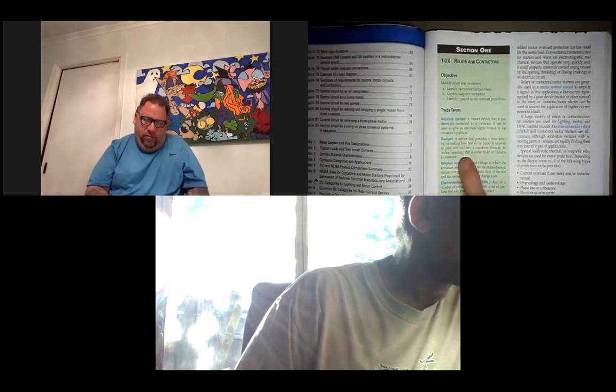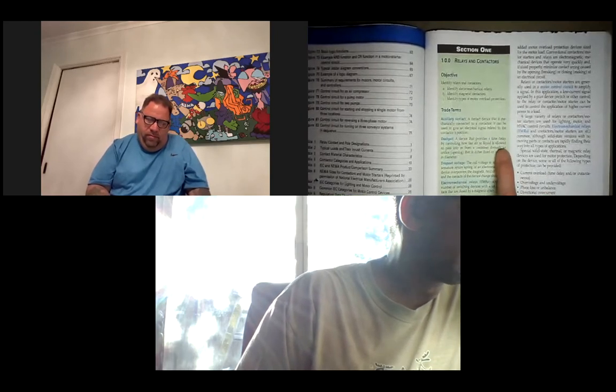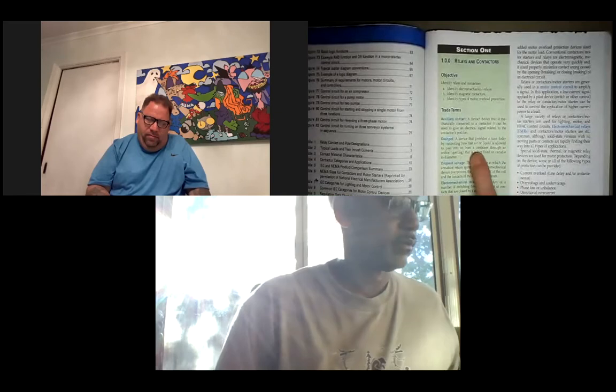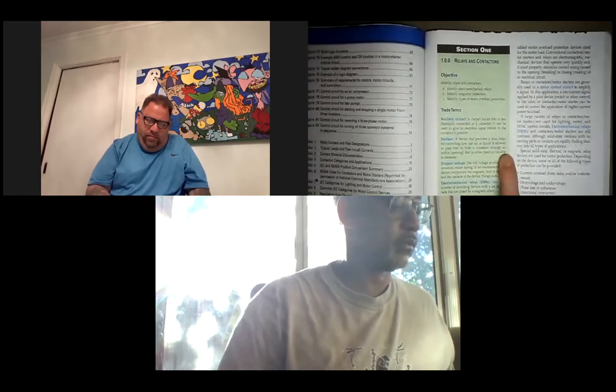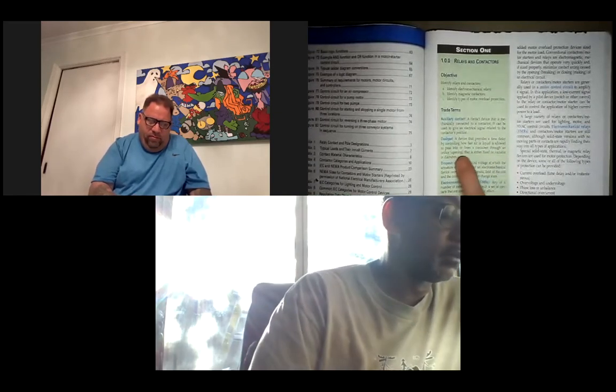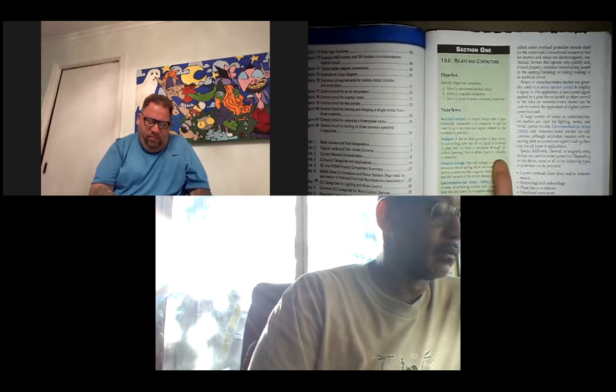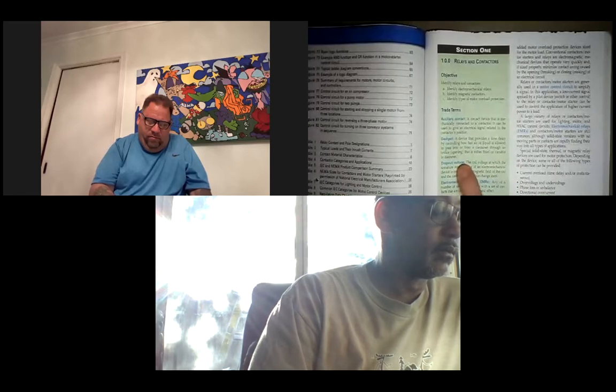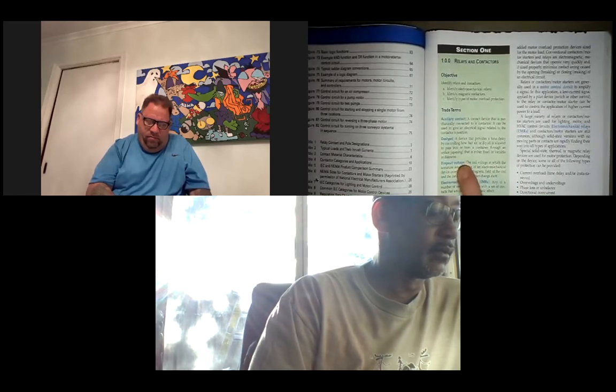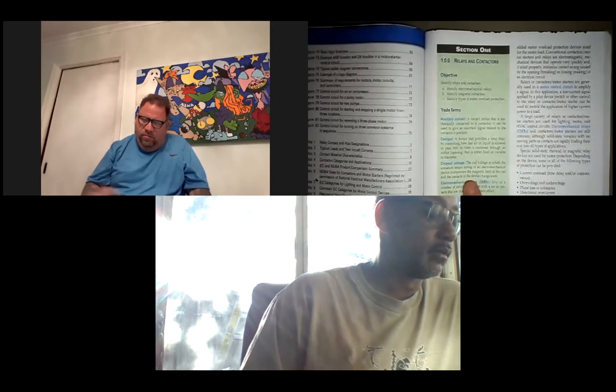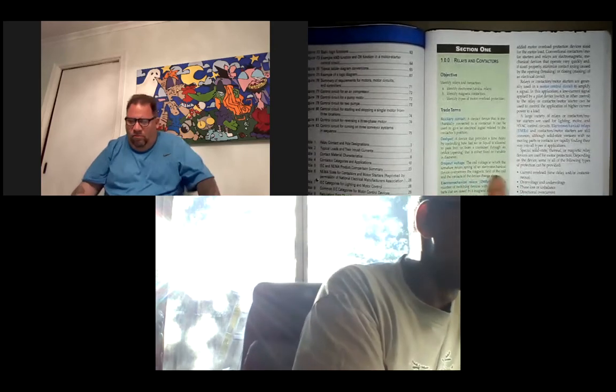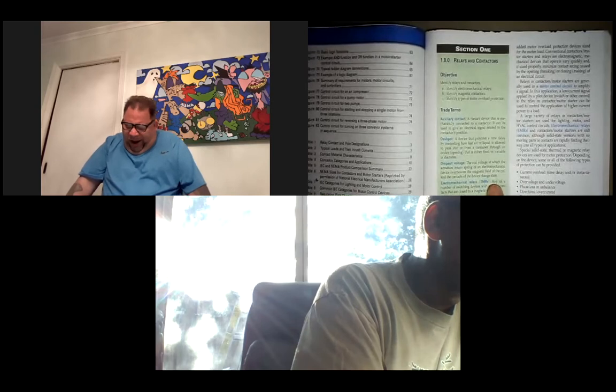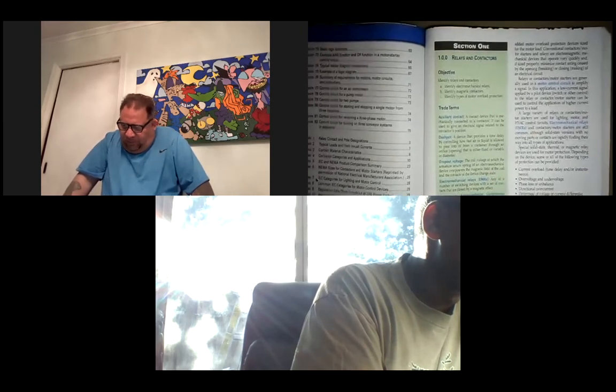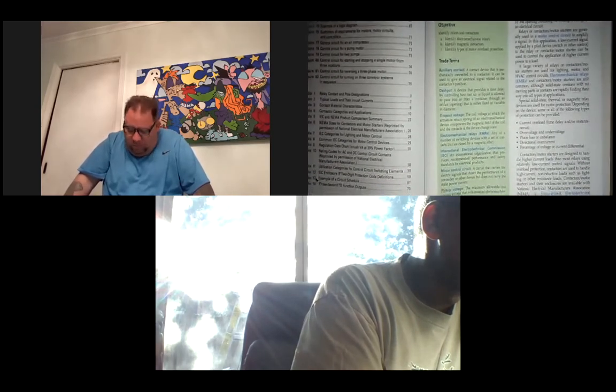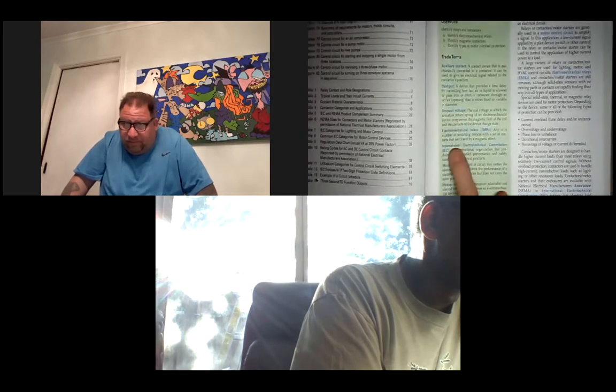Dashpot is a solder pot. It's got solder in it. It's a device that provides a time delay by controlling how fast air or liquid is allowed to pass into or from a container through an orifice that's either fixed or variable in diameter. So that's a timing relay. That's a dashpot. Dropout voltage, basically, it's the minimum amount of voltage that'll keep a contactor sealed in, and if you drop below that, it will drop out.